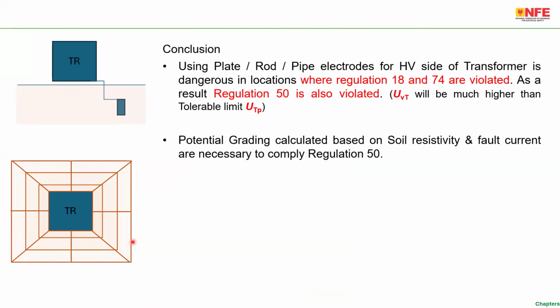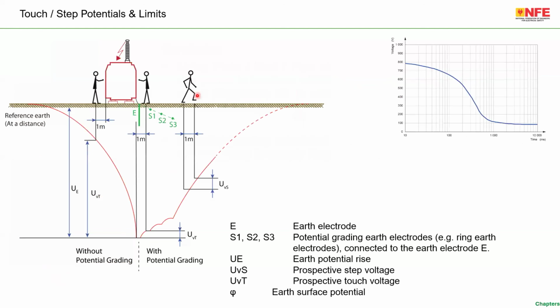So an example, something like this, as I said, the first ring is maybe 1 meter away from the transformer, but 200 to 300 millimeters below. The second one is 3 meters away from the first ring, 1 meter below. The third one is again 3 meters away from the second ring, again 0.5 meter below. So basically, this is the way voltage grading has to be carried out, as you can see in this particular picture. So you see here S1, S2, S3.